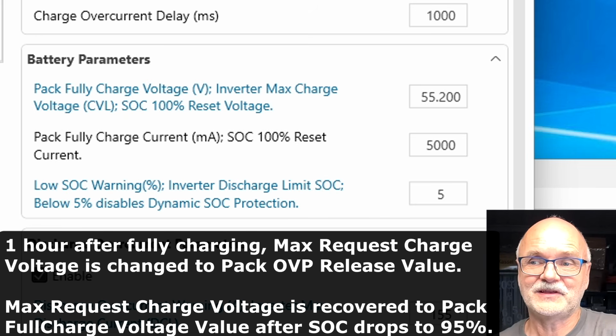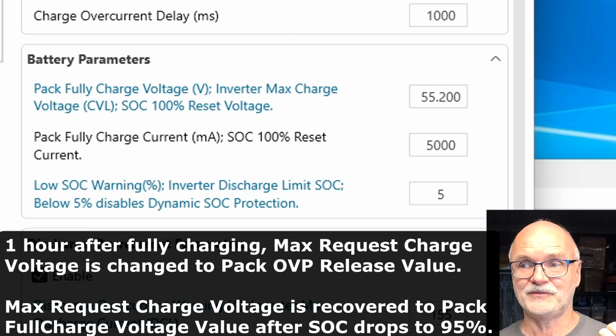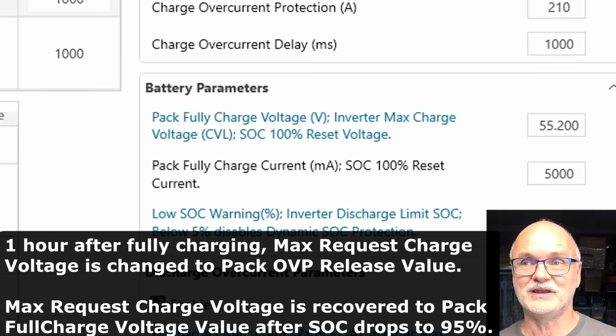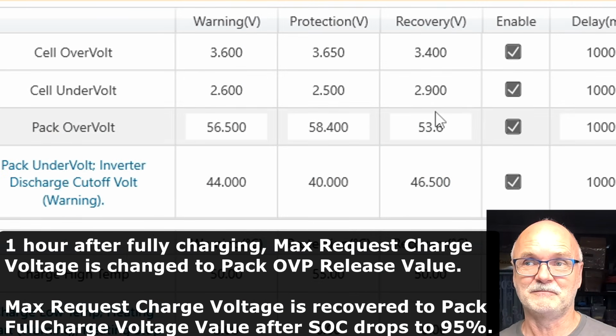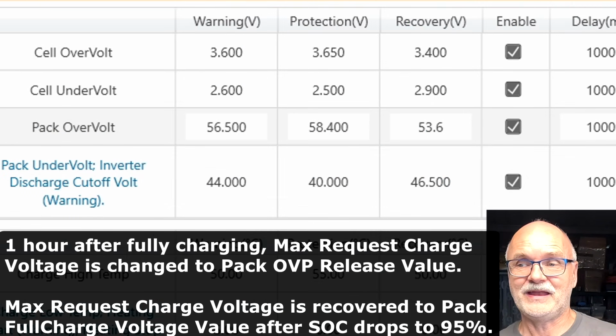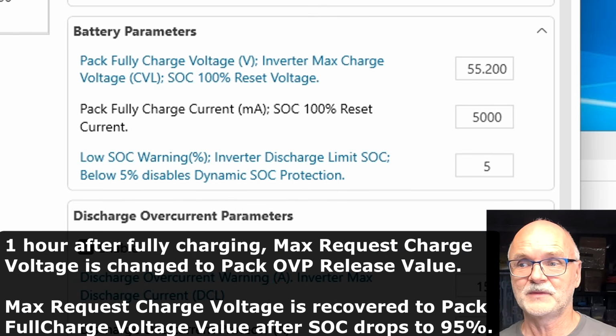This is basically what the text down here means: 1 hour after fully charging at 55.2 volts and less than 5 amps, charge voltage is changed to pack over voltage protection release - that's what we've done. And then maximum request charge voltage is recovered, meaning it goes back from 53.6 to 55.2.